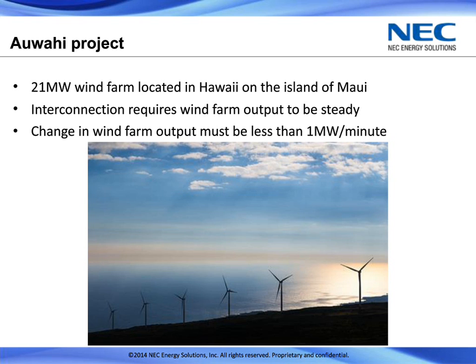And so because of that, the utility there is very concerned about the volatility that you get from these renewable assets. And in essence, in order to deal with the change coming from renewables, their traditional generators have to respond with a ramp in the opposite direction. So their interconnections are set up requiring more stable output from those renewable resources, in this case a wind farm, and in order to achieve that, the power producer is installing battery systems to meet those ramp rates.